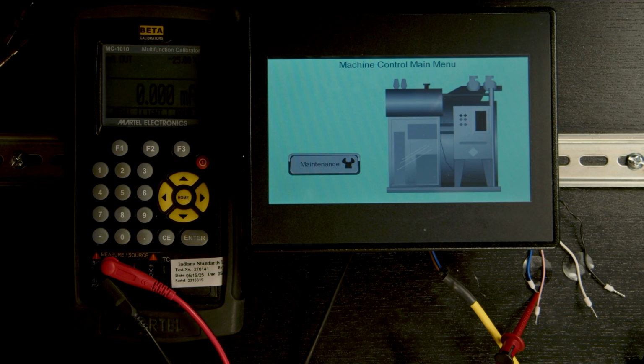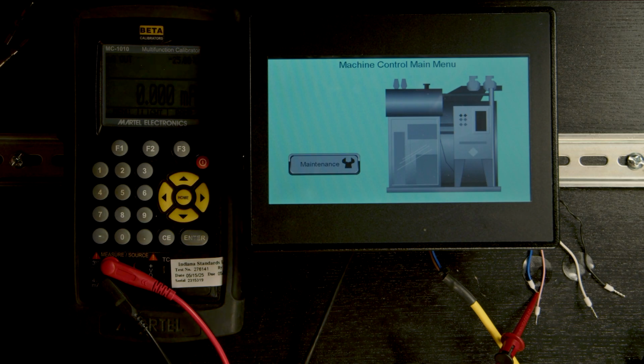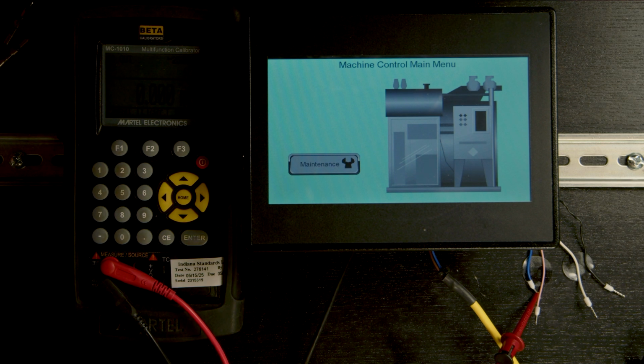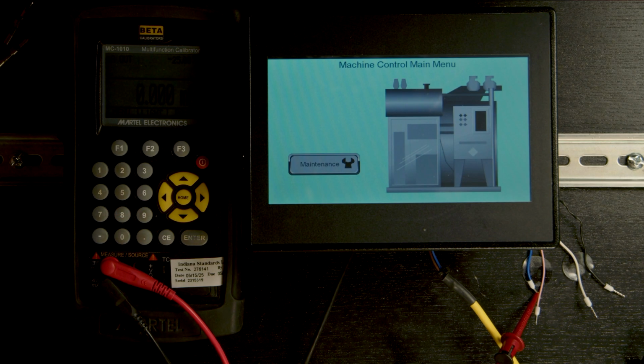Let's demonstrate the field calibration procedure that's built into the micro OCS family. Now, this capability is not available in all Horner products, just the micro OCS, and we're demonstrating it on a micro OCS X7. As I've mentioned before, one of the keys to this is you must have an appropriate instrument.